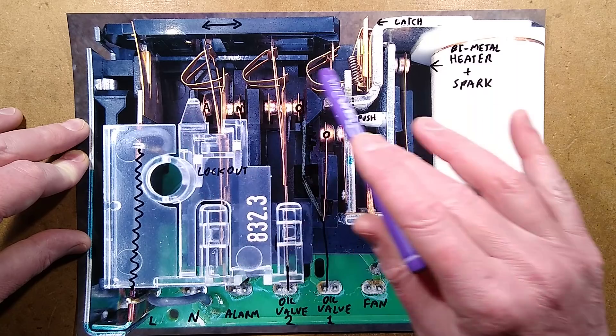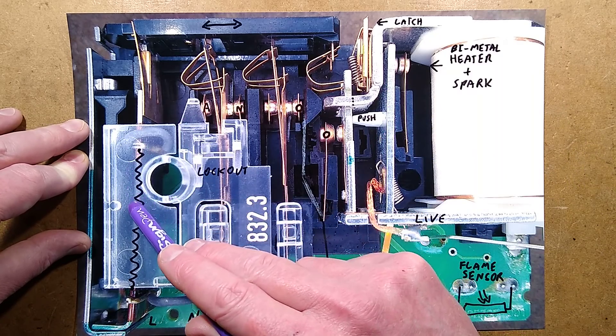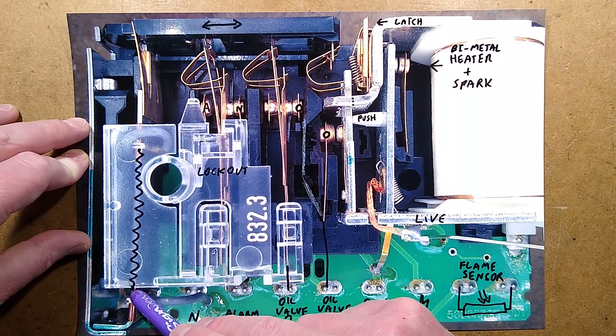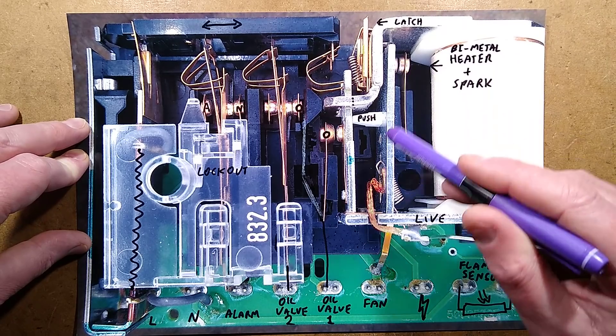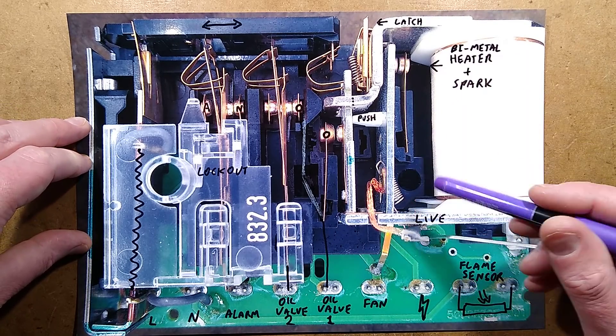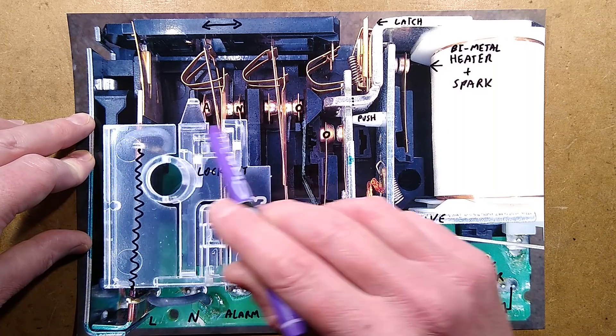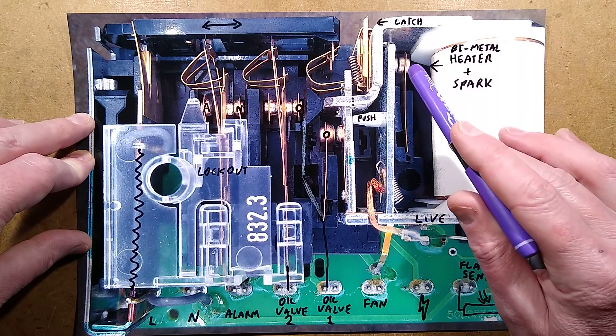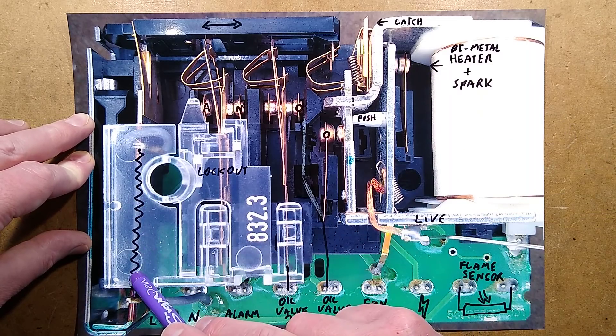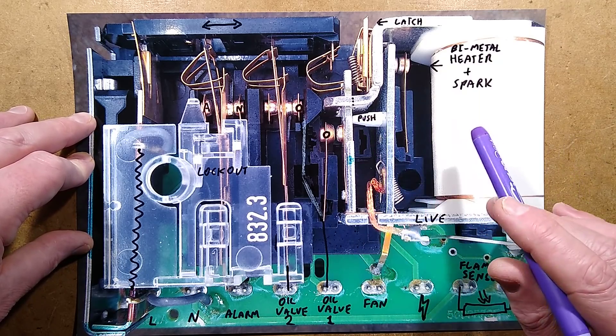The whole mechanism is operated by two devices. There is a bimetallic strip with a heater at this end of the unit, and it is switched through this contact here, which is normally closed when it's all powering up. Two things can happen: either the bimetallic strip can be activated, and if everything goes to plan, this contact will then open at the end. That won't just kill the heater in the bimetallic strip, but it'll also kill the ignition spark. However, if things don't go to plan...